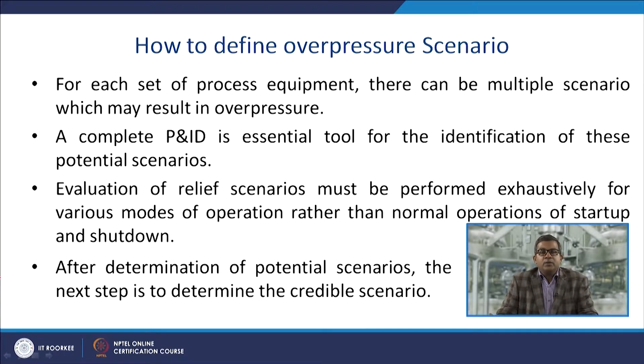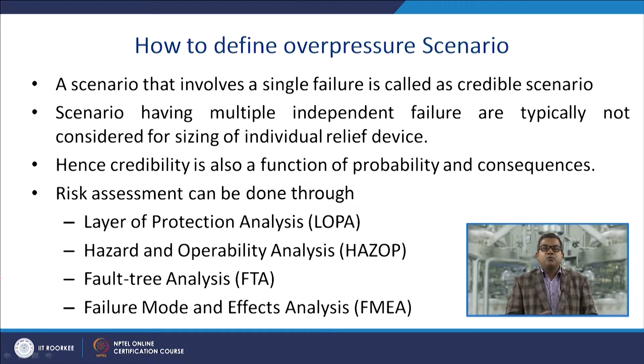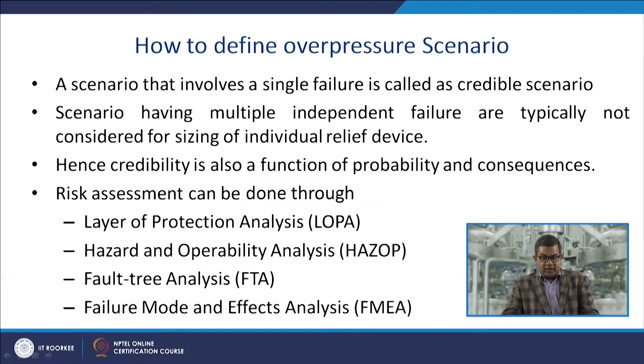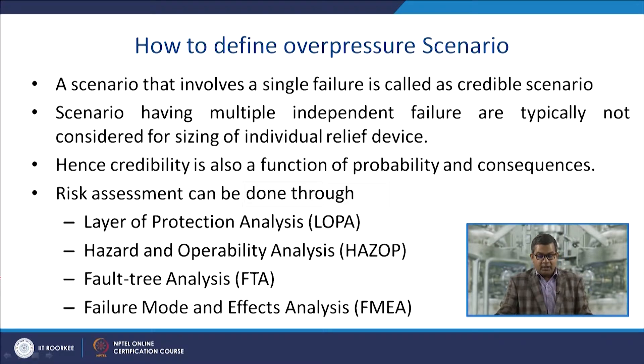After determining potential scenarios, the next step is to determine the credible scenario. A scenario involving a single failure is called a credible scenario, while scenarios with multiple independent failures are typically not considered for sizing individual relief devices. Credibility is a function of probability and consequences. Risk assessment methods include Layer of Protection Analysis (LOPA), Hazard and Operability Analysis (HAZOP), Fault Tree Analysis (FTA), and Failure Mode and Effects Analysis (FMEA).